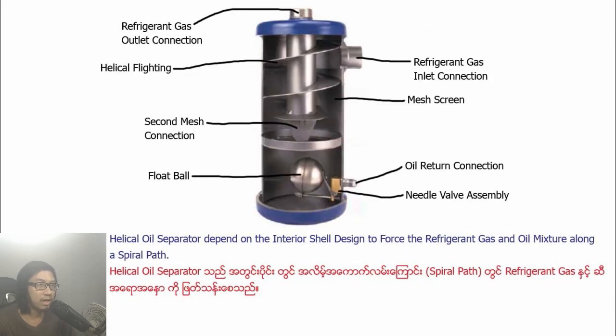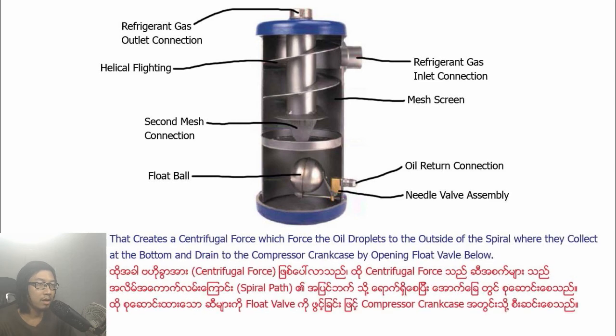Helical oil separators depend on the interior spiral design to force the refrigerant gas and oil mixture along a spiral path. They create a centrifugal force which forces the oil droplets to the outside of the spiral, where they collect at the bottom and drain to the compressor crankcase by opening the float valve below.